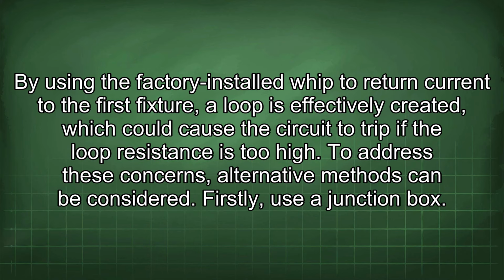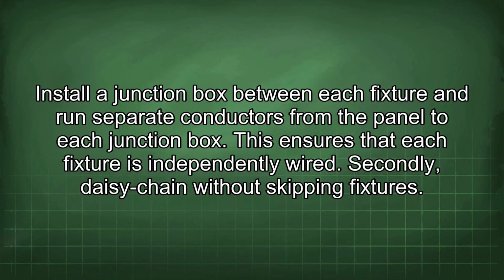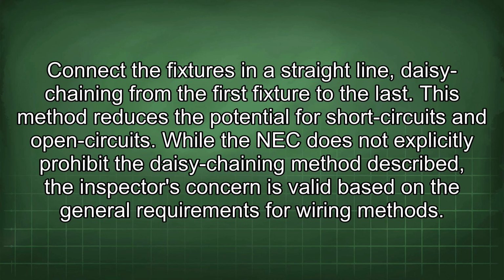To address these concerns, alternative methods can be considered. Firstly, use a junction box. Install a junction box between each fixture and run separate conductors from the panel to each junction box. This ensures that each fixture is independently wired. Secondly, daisy chain without skipping fixtures. Connect the fixtures in a straight line, daisy chaining from the first fixture to the last. This method reduces the potential for short circuits and open circuits.